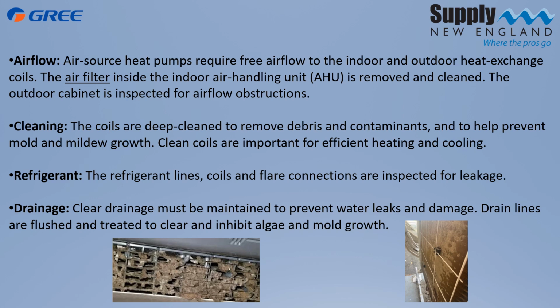When we're there, we're going to be doing some things. We're going to be checking, make sure the indoor fan is clean. You know, those things are full, those are scoops, right? And if your scoops are full of debris, it can't scoop and move the air. So we're going to make sure that that's clean. We're going to check the filters, make sure the filters are clean. We're going to look at the indoor and the outdoor coils, clean them if they need to be.